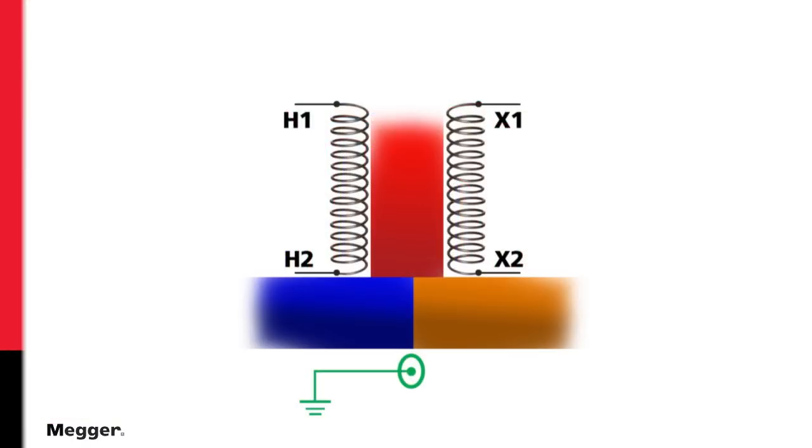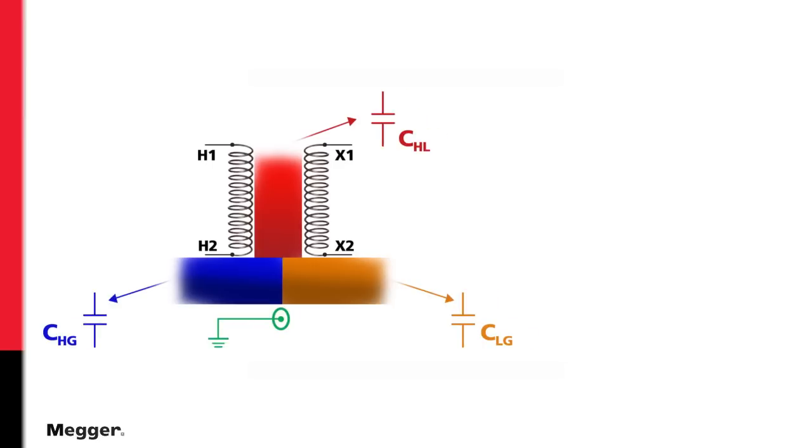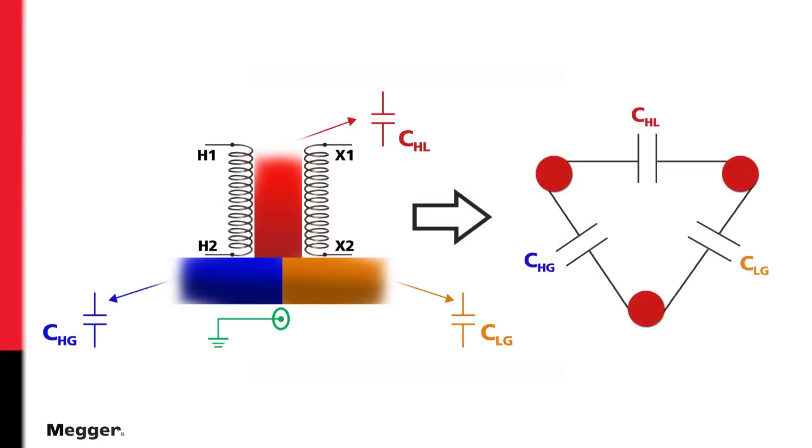For a typical two winding transformer, we are interested in three key insulation measurements: high winding to low winding, high winding to ground, low winding to ground. Some newcomers to this test assume we test between phases, but it is between windings where test is conducted, as well as winding to ground.